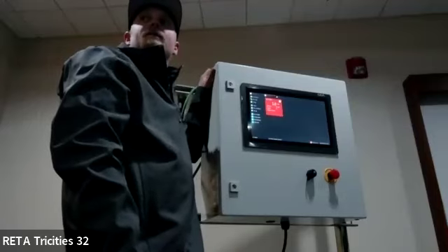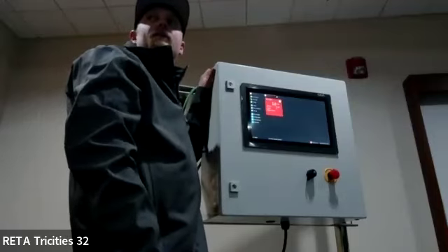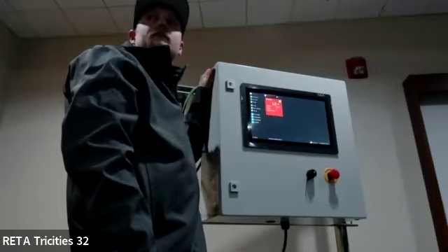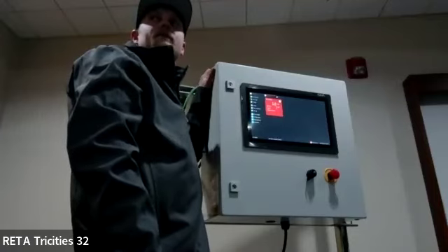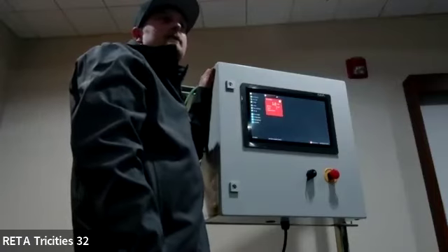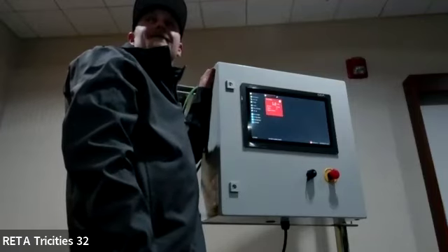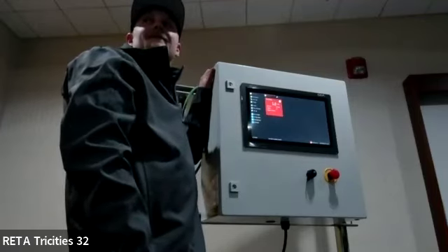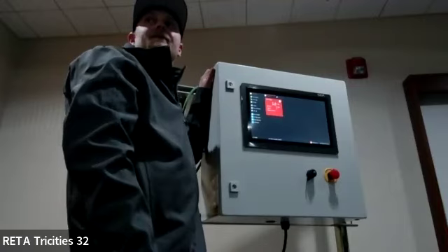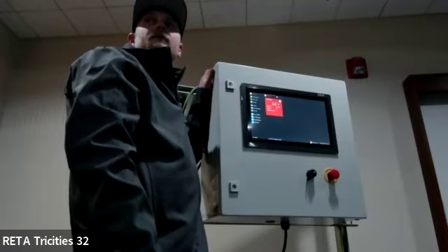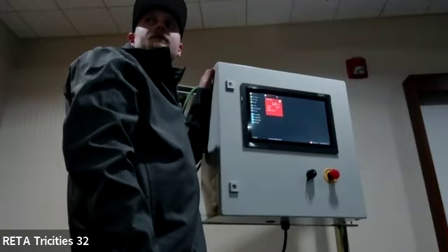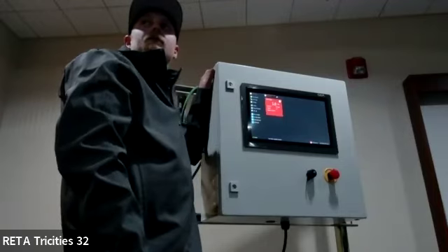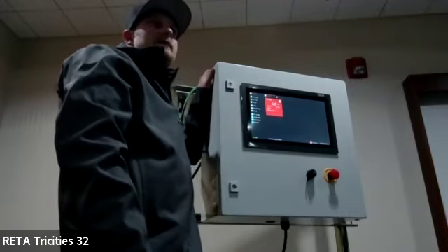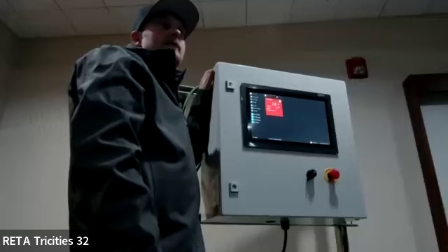Unless they're networked, you can't do it. There's got to be a Cat5 cable that goes compressor to compressor, or it's got to be networked to a switch. If you don't have a control system, it's very easy to run Cat5 between the several panels and use this as a control system. You enter one set point and it'll be the master and control all the rest of it. Has to be configured, but it can do that.